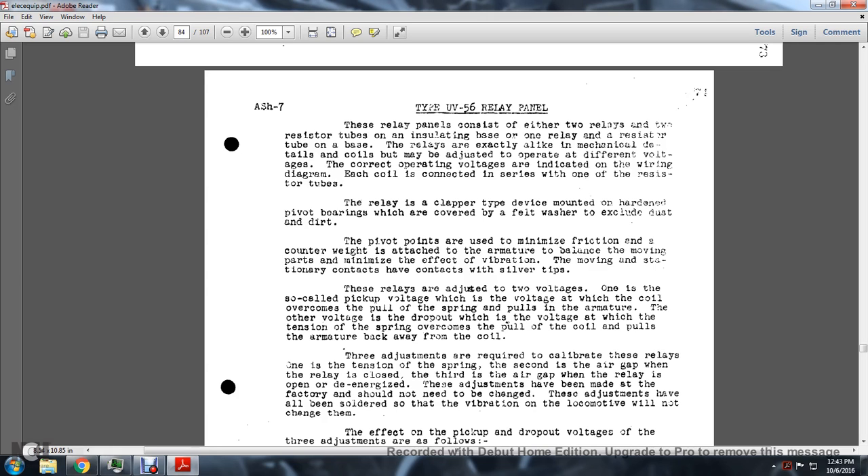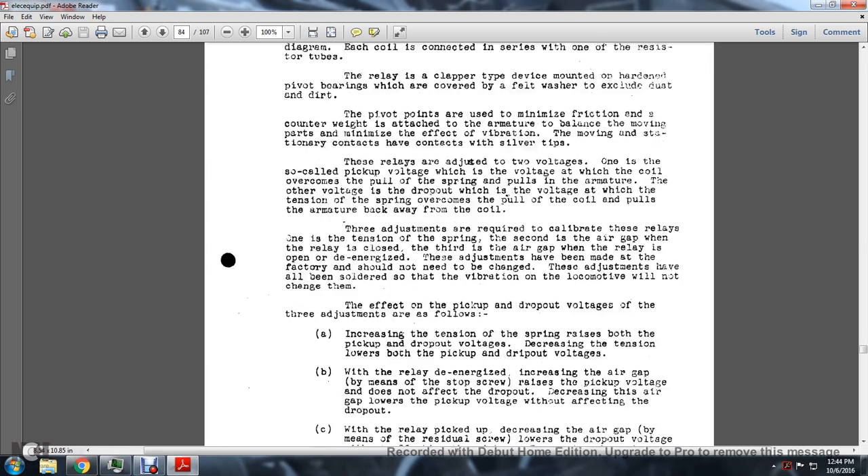The moving and stationary contacts have silver tips. These relays are adjusted for two voltages: the pickup voltage, at which the coil overcomes the pull of the spring and pulls in the armature; and the dropout voltage, at which the spring tension overcomes the coil pull and returns the armature. Three adjustments are required: (1) tension of the spring, (2) air gap when the relay is closed, and (3) air gap when the relay is open. These adjustments are made at the factory and should not be changed; they are soldered so that vibration on the locomotive will not change them.